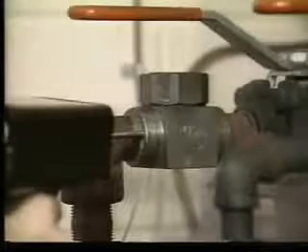If the trap is working too rapidly, it may indicate a sizing problem. The sound of motorboating indicates wasted steam. When this trap fails, it generally fails open and a continuous rushing sound is heard.